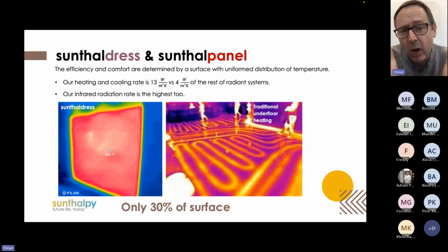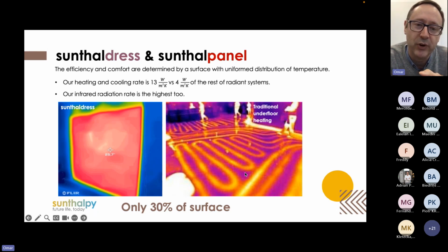There's a loss of performance, and the huge loss is because between the tubes, that intermediate surface is working at a much lower temperature, since the concretes and mortars used for underfloor heating have low conductivity. So in the end, we can have a huge surface, but only some part of it is actually working.